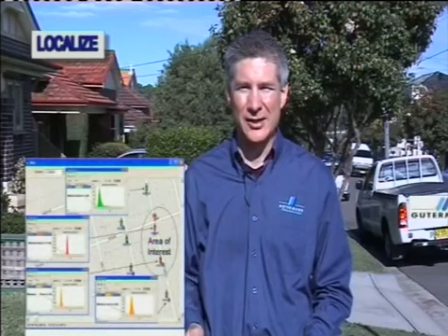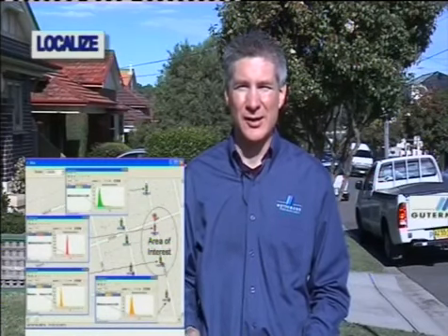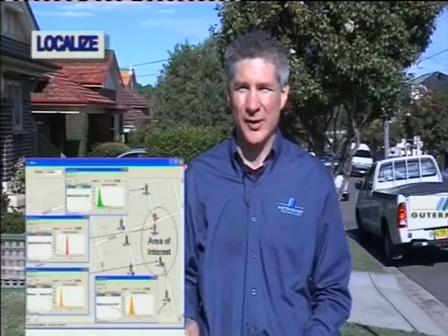So now that we're looking at the results, we can see that there are 3 loggers indicating the probability of there being a leak in the section of Duchess Street, and the loudest readings up on the corner of Duchess and First Street. So now with the noise logging results, which have localized the position of the leak to the corner of Duchess and First Street, it's time for us to think about locating the leak. So we move into the location stage of LLP.